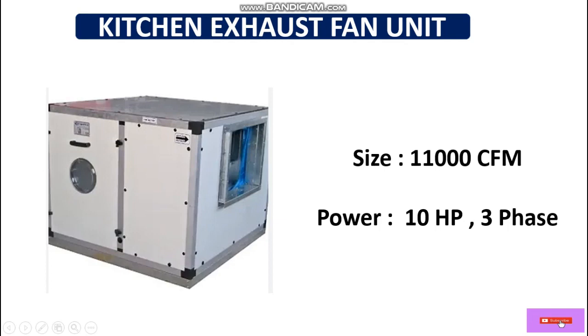So the capacity of the motor of this exhaust fan unit is 10 HP, which is more than 5 HP. That's why we have to use the star delta starter or VFD drive. So here we are going to calculate the size for the contactor for the star delta starter.